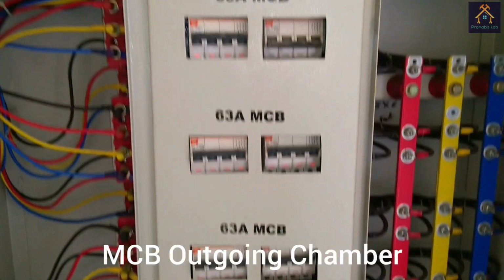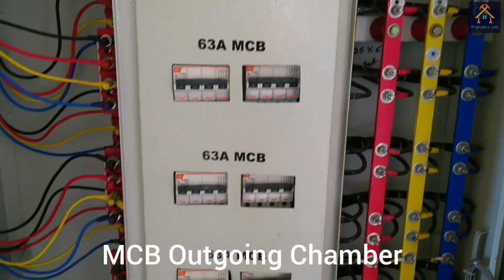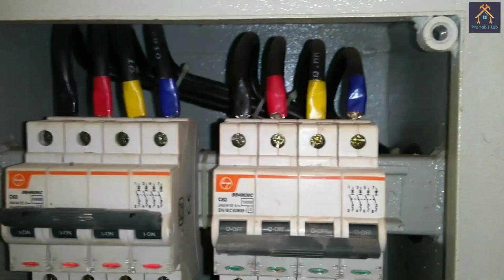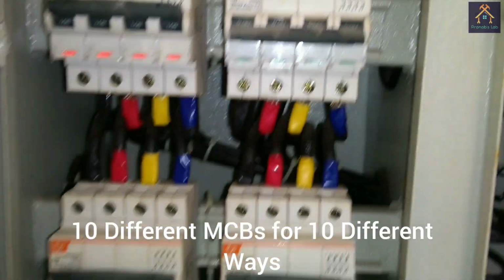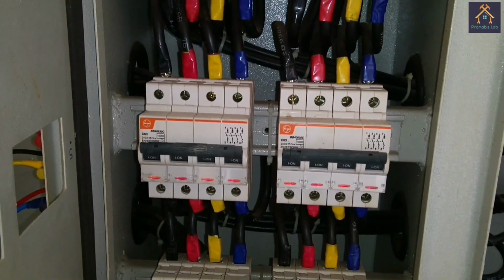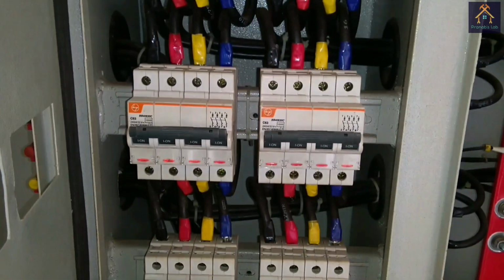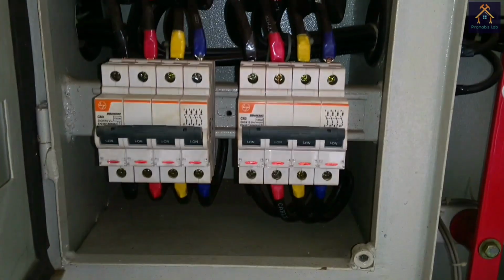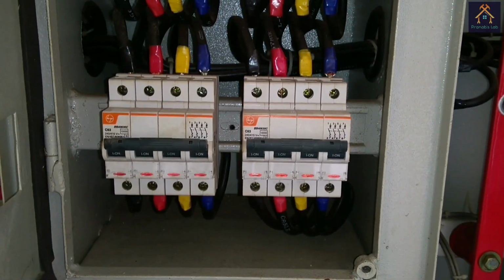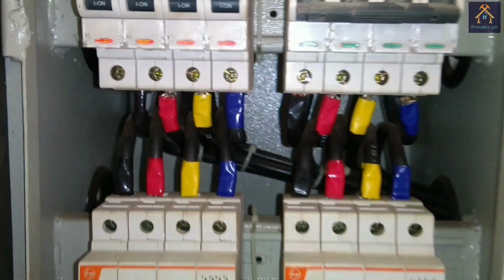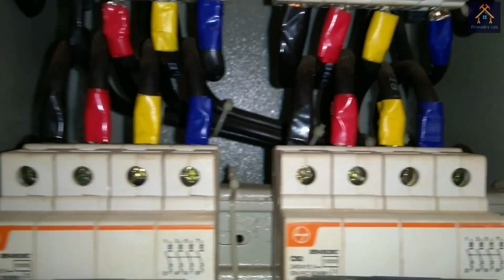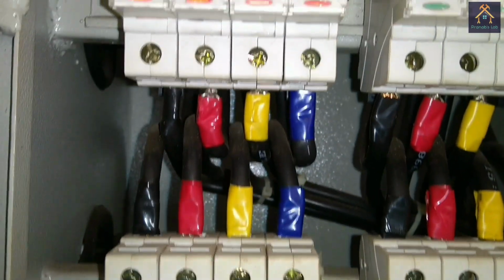The next chamber is the MCB chamber. There are a total of 10 MCB units for 10 different ways. Each set of tappings is taken from the bus bar and inserted into the input point of the MCB, and in each row there are 2 MCBs mounted on the DIN rail. The 4 output terminals are coming out from the MCBs and inserted into the next chamber.